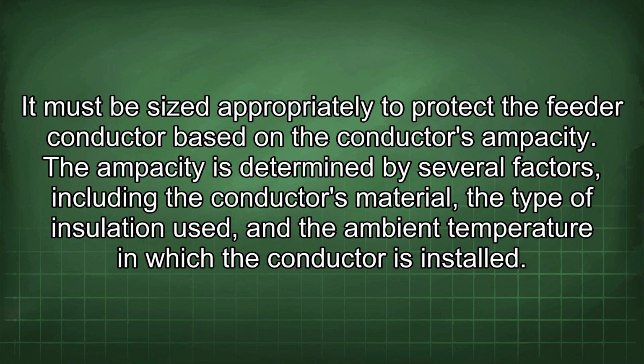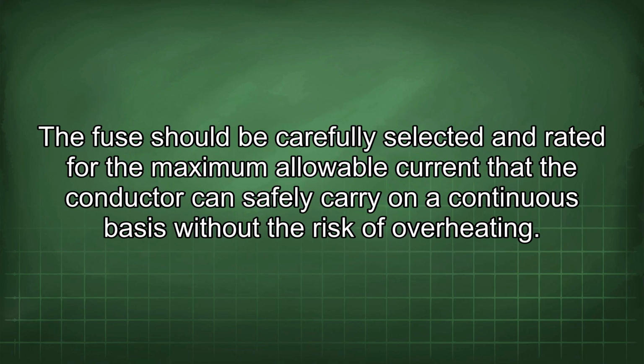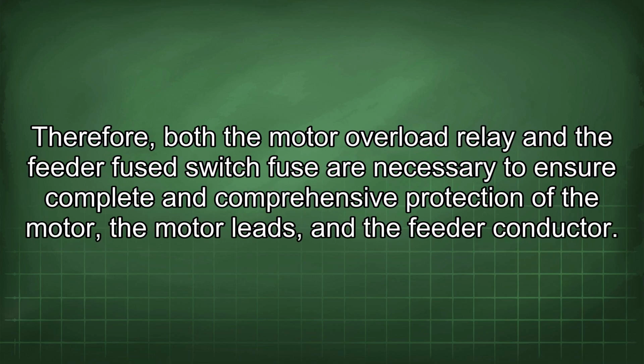The ampacity is determined by several factors, including the conductor's material, the type of insulation used, and the ambient temperature in which the conductor is installed. The fuse should be carefully selected and rated for the maximum allowable current that the conductor can safely carry on a continuous basis without the risk of overheating. Therefore, both the motor overload relay and the feeder fused switch fuse are necessary to ensure complete and comprehensive protection of the motor leads and the feeder conductor.